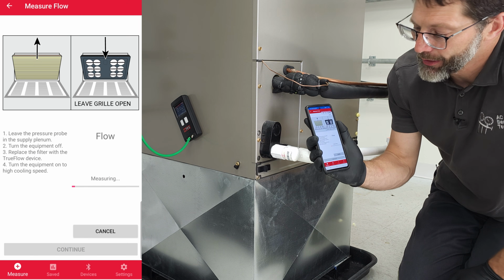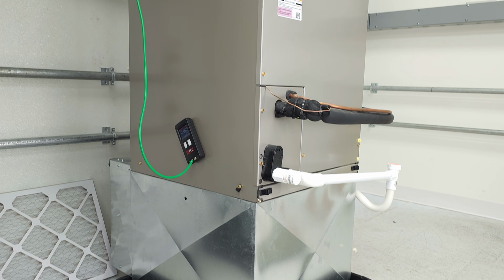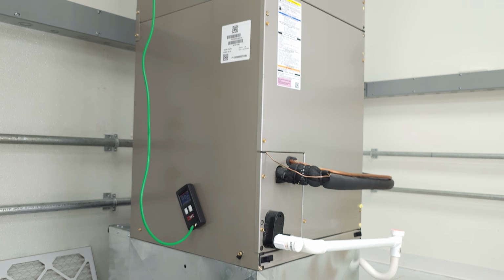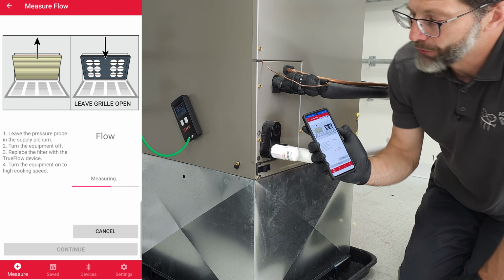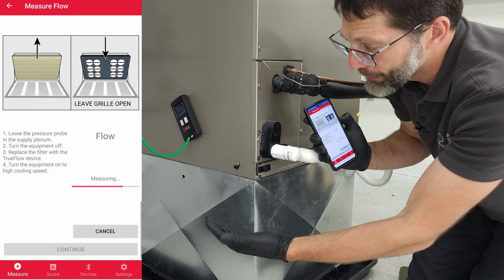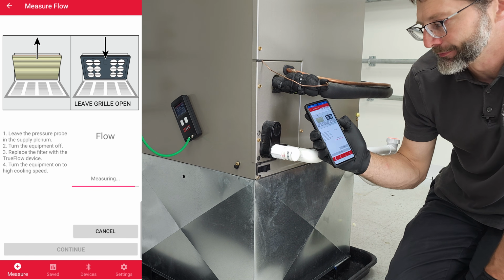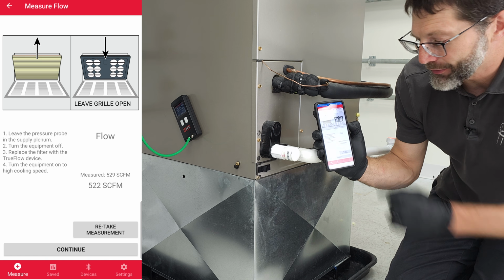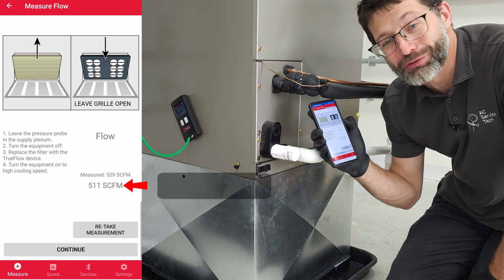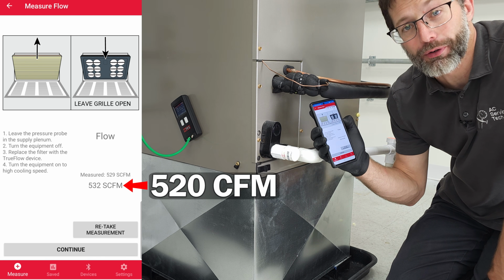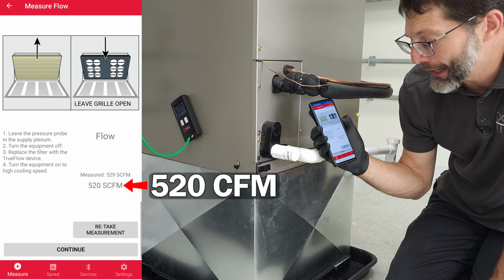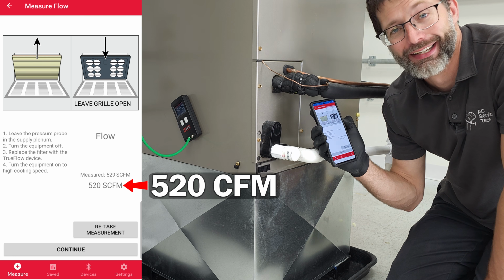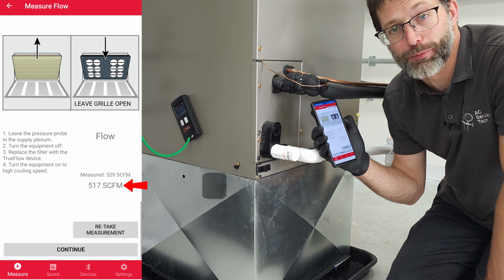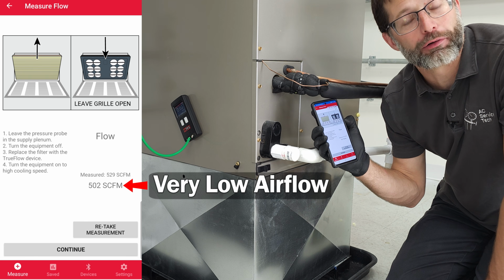Now we're going to click take measurement. So you just want to make sure that you have the TrueFlow grid facing in the correct direction. Of course, the back here is just an open hole where we're located at. And so you can see our CFMs is extremely low. So the cubic feet per minute that we have is 520. It needs to be 1200 CFMs. That's how bad of airflow we have.